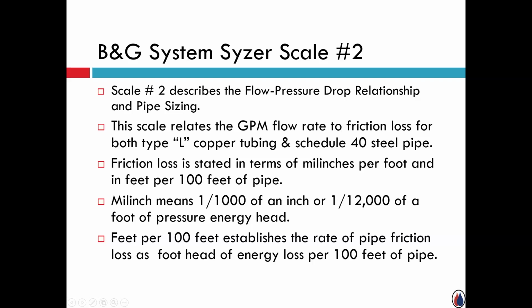But Scale 2 references 2 types of pipe, Type L copper tubing and Schedule 40 steel pipe. There's 2 terms that they're going to use, milli-inches per foot and then feet per 100 feet. The milli-inches comes from days gone by, years and years ago. We're never using that. You're never going to see it today, at least in calculating head loss, friction loss, in a closed loop system. But years and years ago, when the industry was transitioning from gravity hot water to pumped forced circulation, the pipe sizing was tremendously big, and it had to be for gravity hot water. There was no circulator. Once they started transitioning and adding a circulator or booster pump, when you were using this existing technically oversized piping, the pressure drop was so low that to have some kind of numbers that made a little bit of sense, they incorporated this milli-inch. It's long gone. It's just there mostly for historical reference.